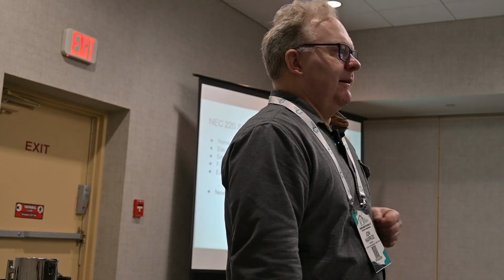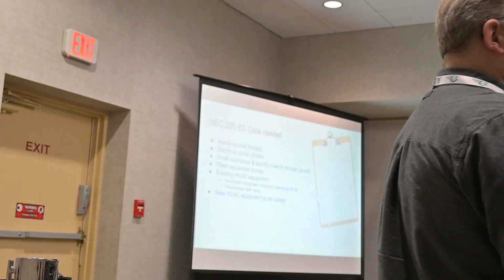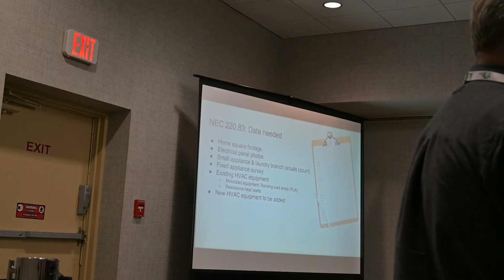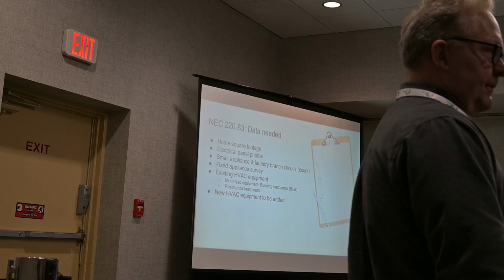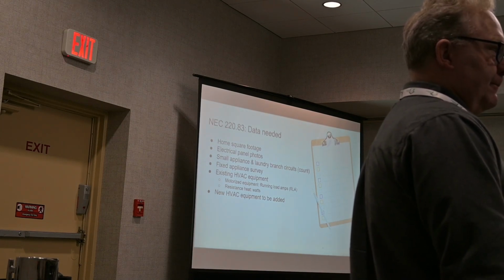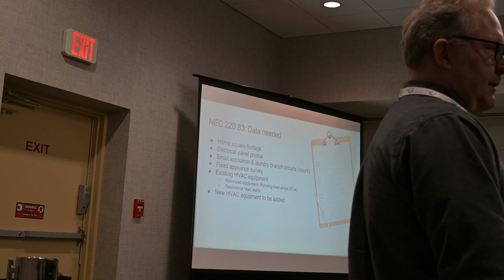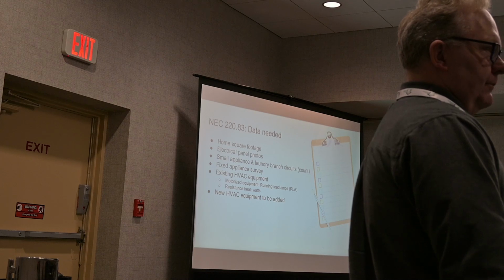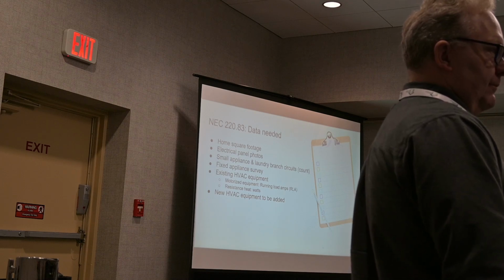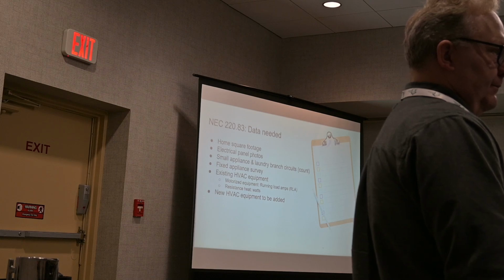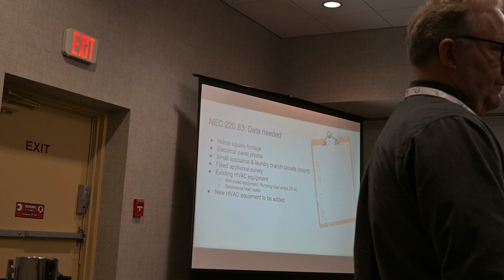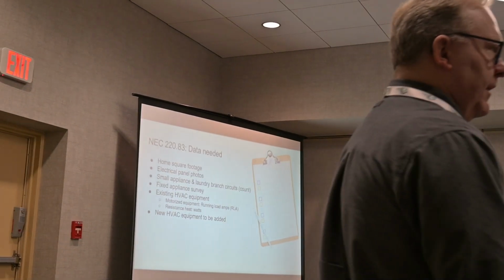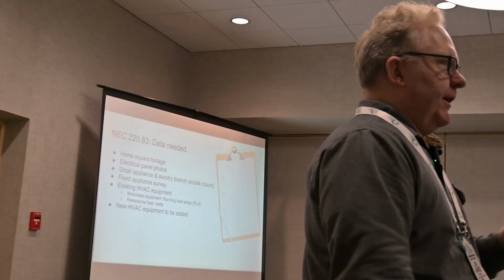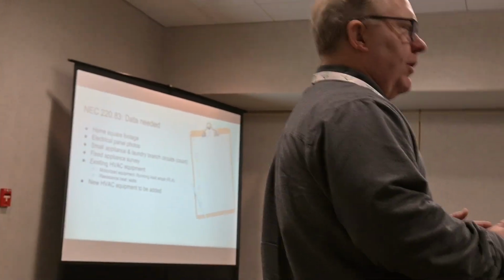I think a good time to mention is something that's up and coming. There's a pilot project now with Span panels. A Span panel is a load shedding panel. The concept is to be able to use some 100 amp services without switching service, where the panel is actually rated at 200 amps and it will shed loads. Yeah, I'm going to mention those really briefly later on, but there are definitely some workarounds if these calculations show that you're over the limit.